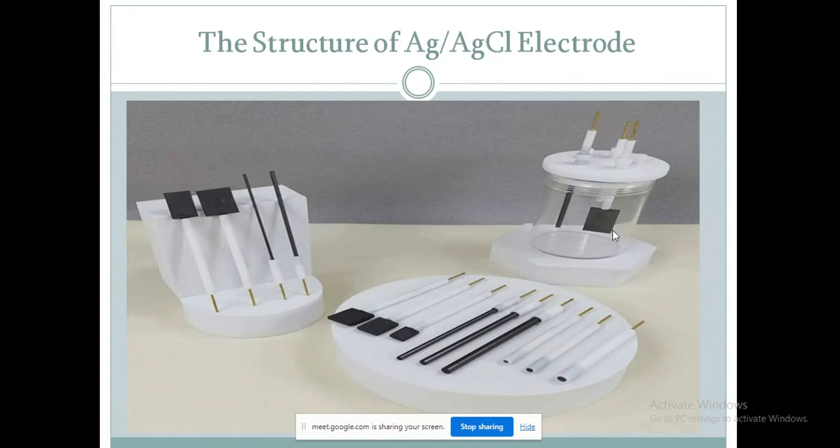Here, the electrolyte, potassium chloride, which is called the salt bridge, serves as the liquid conductor to connect one liquid with the other. The potassium chloride salt bridge is useful to minimize the formation of the concentration gradient, since the potassium and chloride ions possess the same mobility, so the resulting liquid-to-liquid junction potential is minimized.